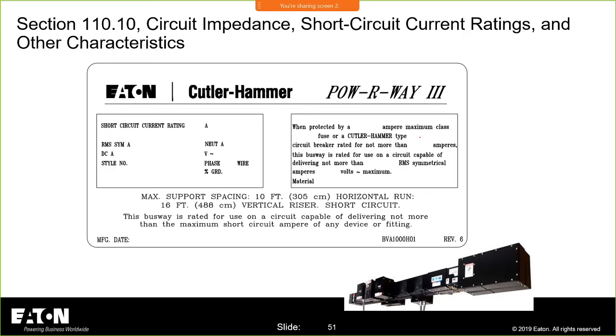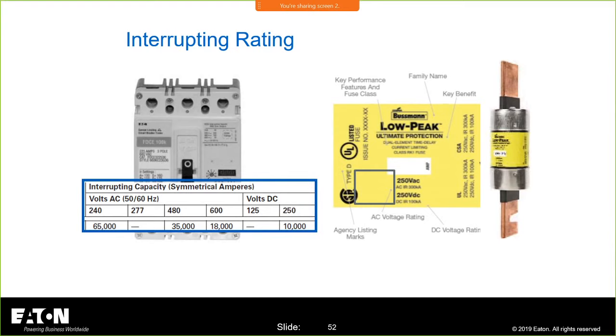So an important aspect of proper application of these devices is to understand what the available fault current is, what the capabilities of the products are, and then do that comparison. In the case of a lot of these devices, they're going to be dependent upon what overcurrent device is applied upstream or internal to, say, a fusible switch. What fuse you put in there could be critical to the short circuit current rating of that equipment, because the current limitation of the fuse and the circuit breaker is what's going to get you that rating. You have to put the right devices.